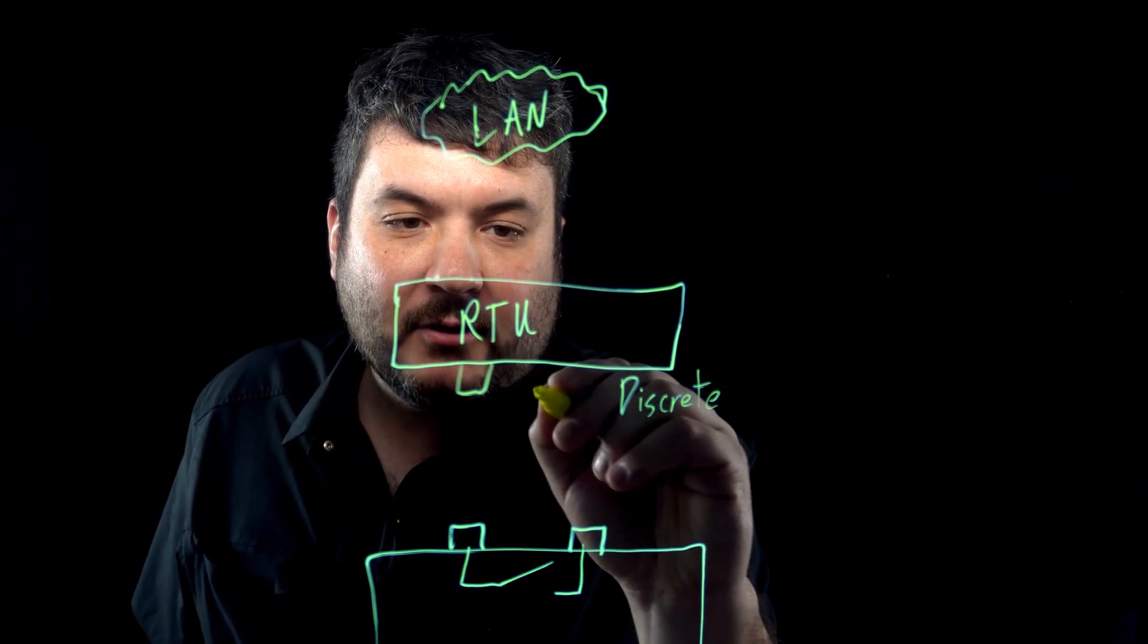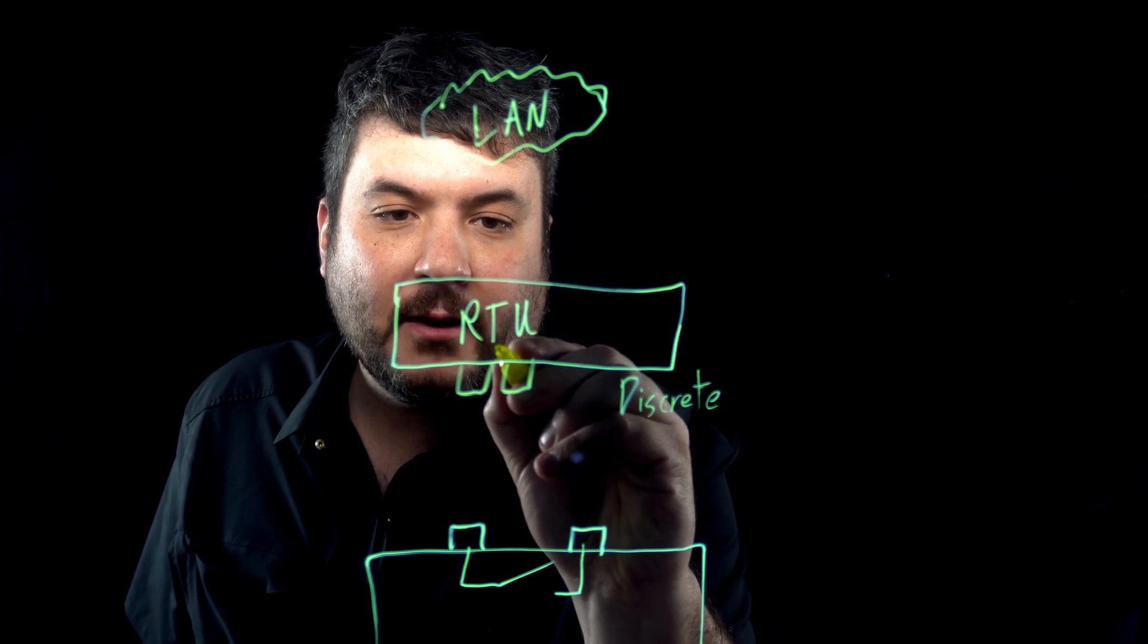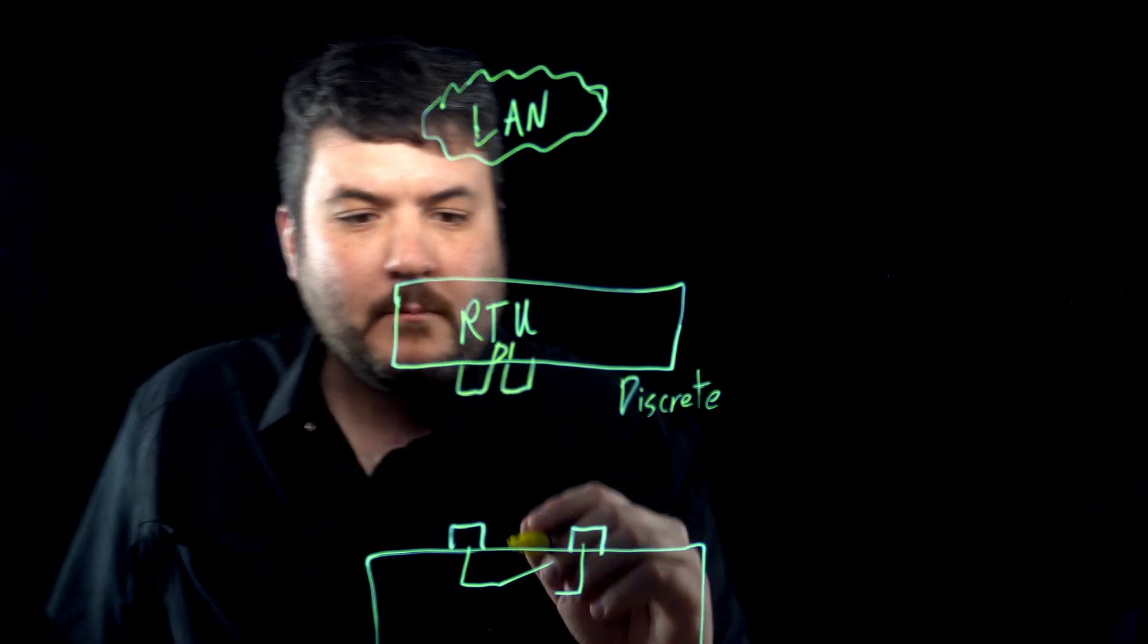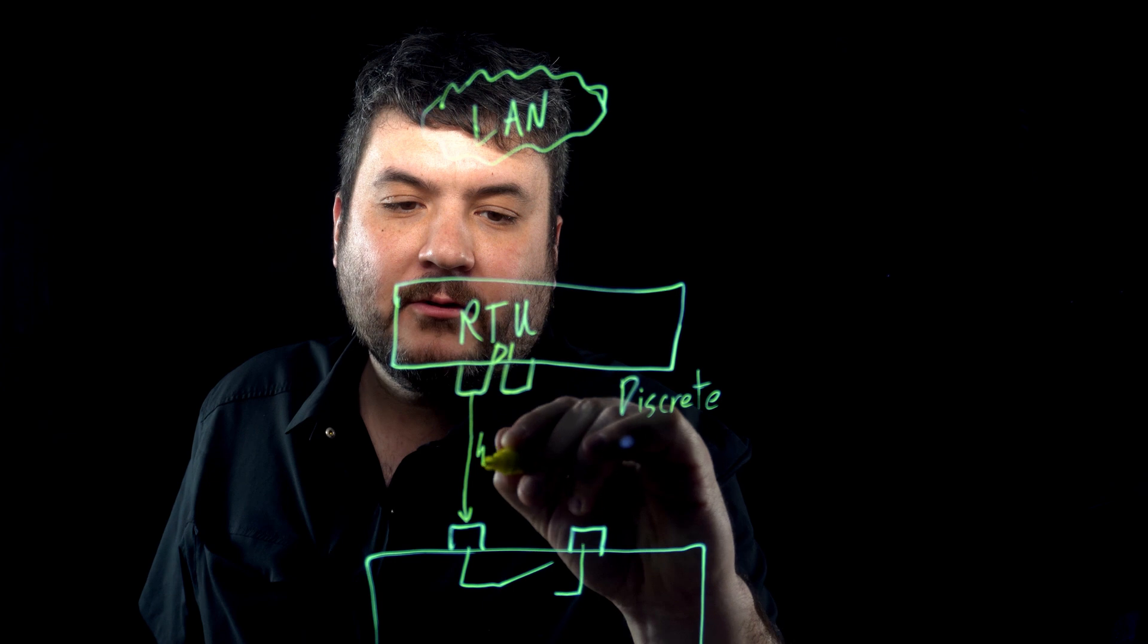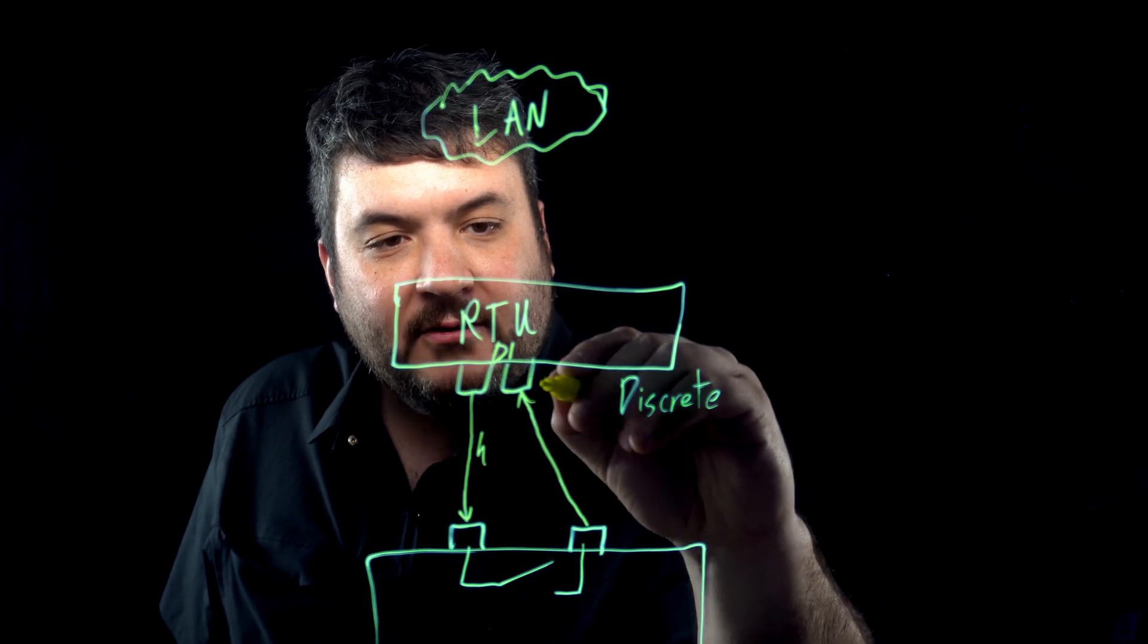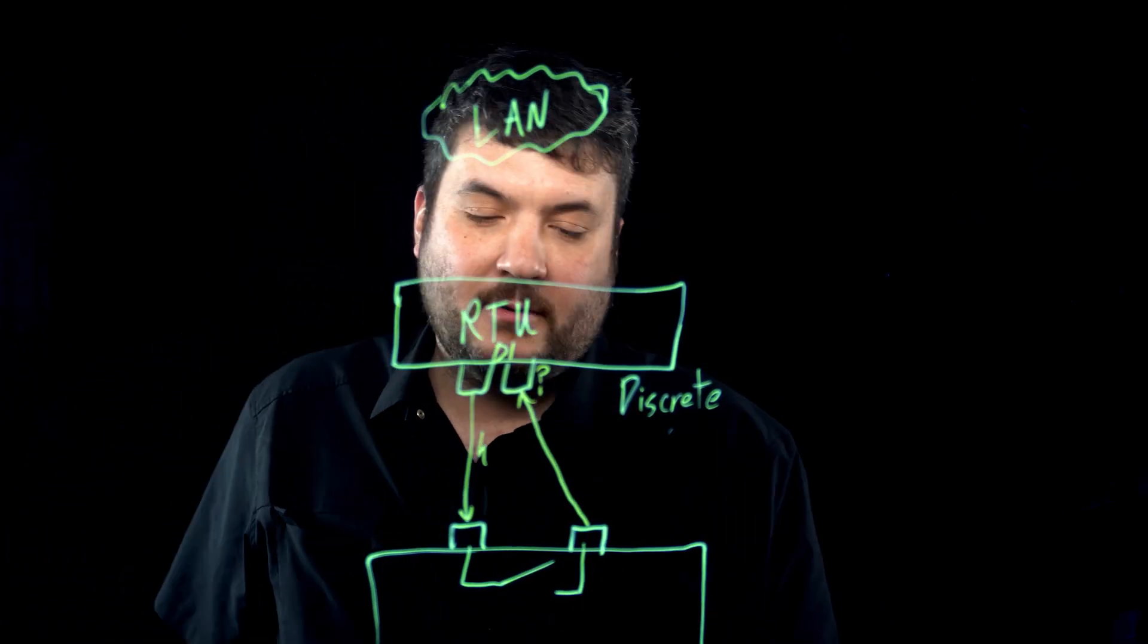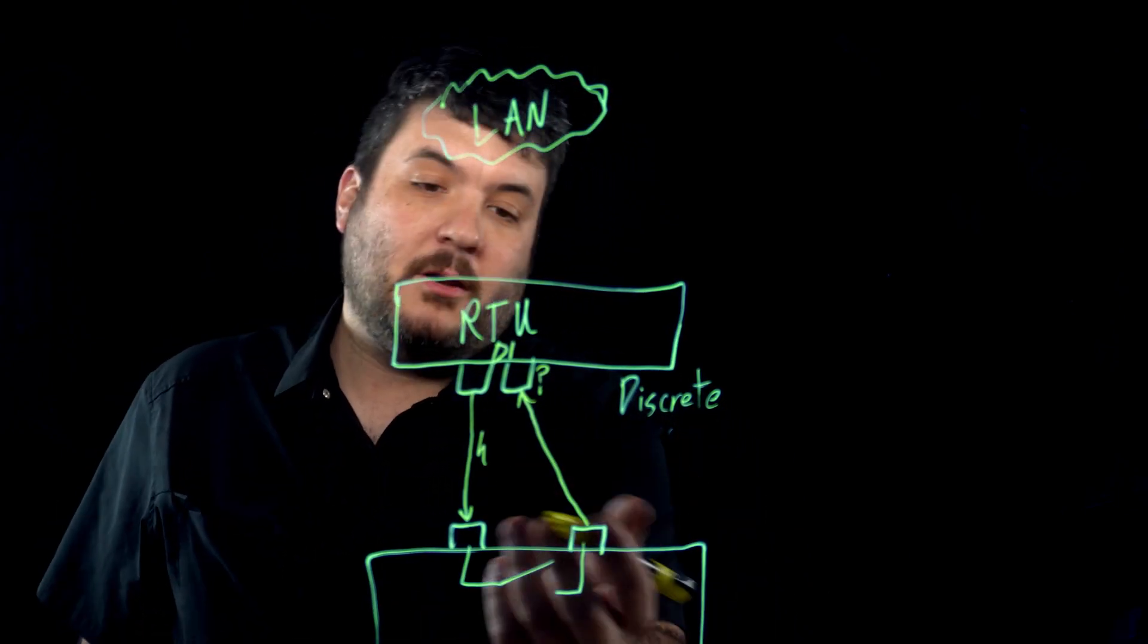So, if we had our first discrete input on this RTU, it might be here. We'll call that, how about D1 for discrete 1. What we're going to do is send a very small electrical charge across a wire there. And then we're going to wire this back. And we're looking to see, do we see anything? If we do have continuity, we know that that relay must be closed. If we don't, we know that it's open.